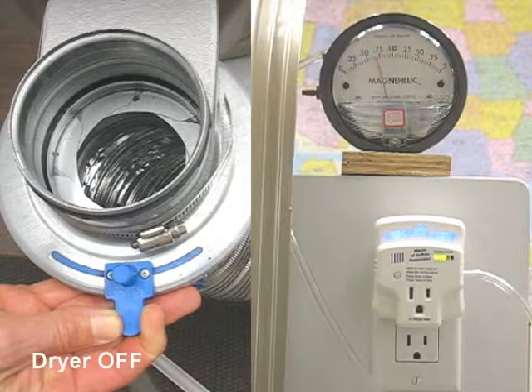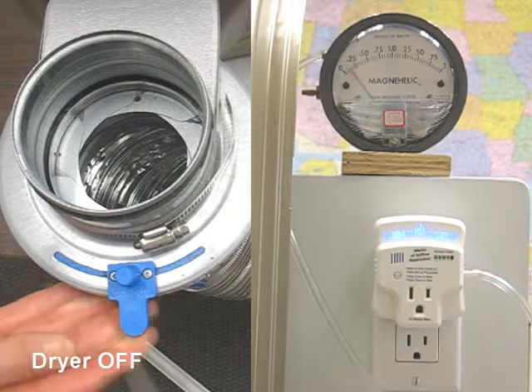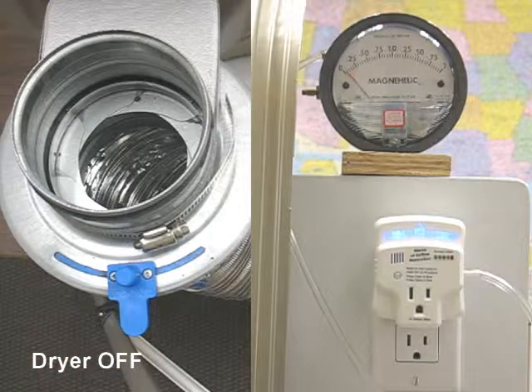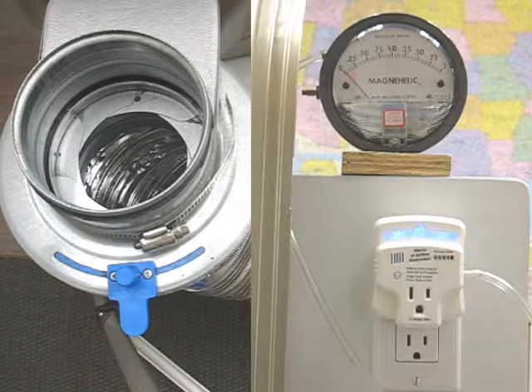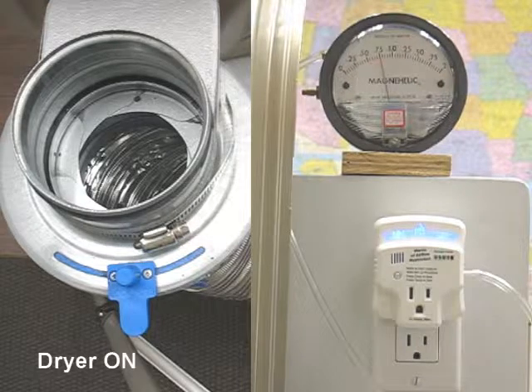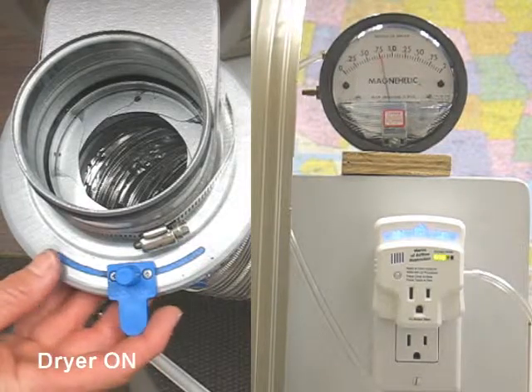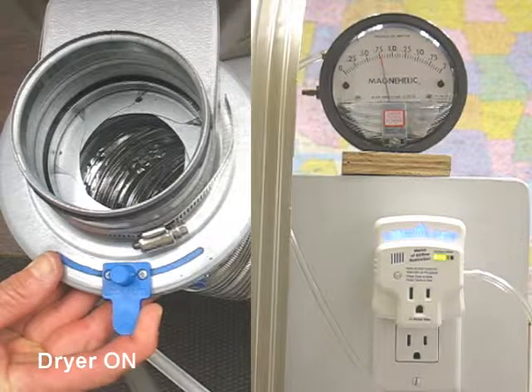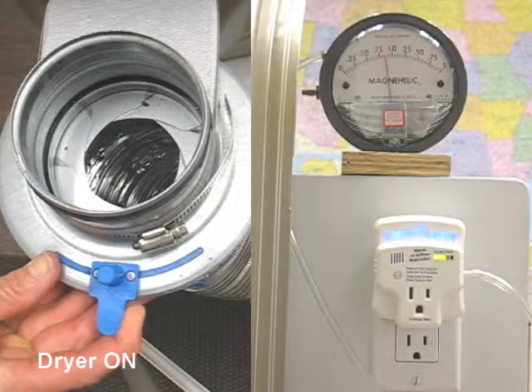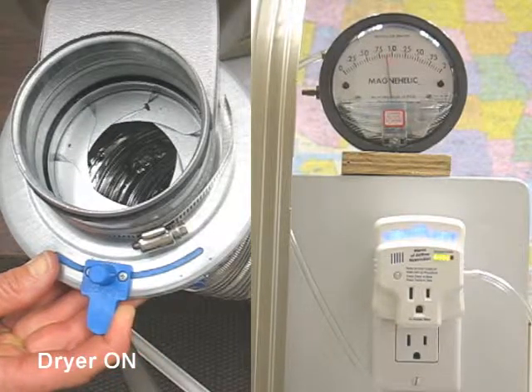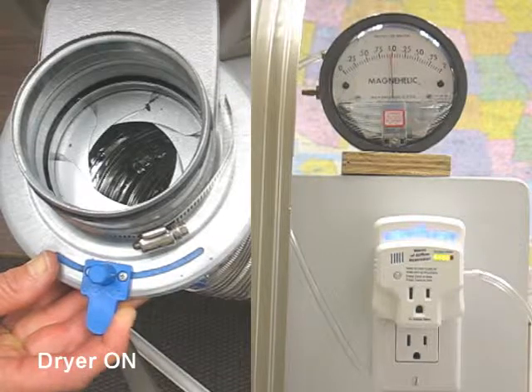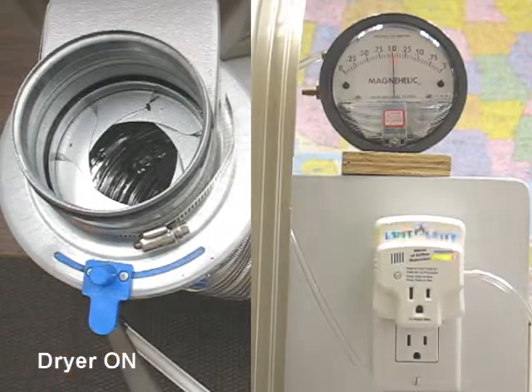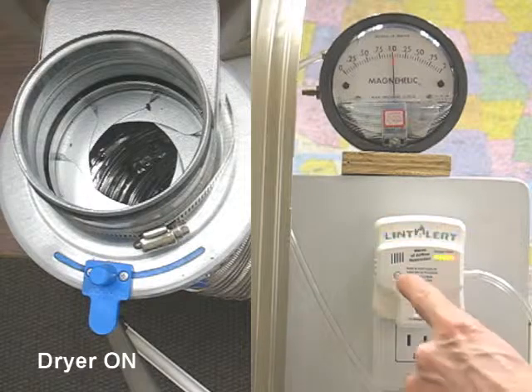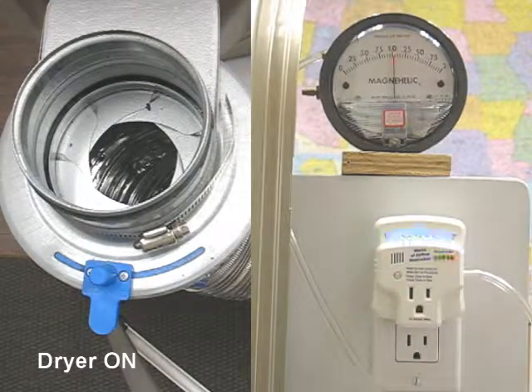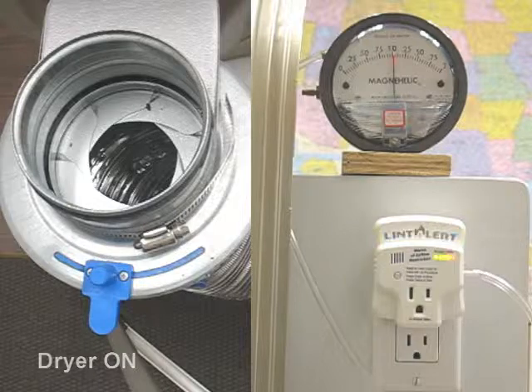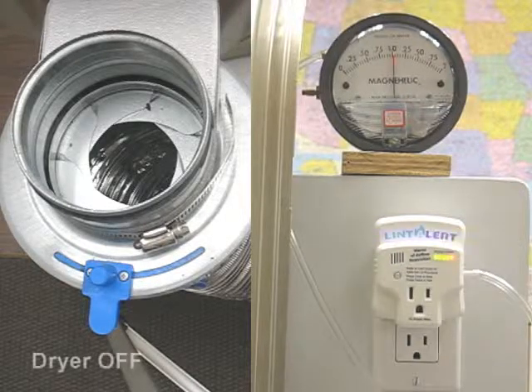If I turn off the dryer, the light bar goes out as no pressure exists. Upon restarting the dryer, the LintAlert reveals that the same levels of back pressure still exist in the system. Over time, as lint continues to build up, so will the blockage indicator until the final stage, which includes the combination of blinking lights and audible tone. The audible tone can be muted with a single push of the button. The blinking will remain as a reminder to assess the cause of the severe back pressure found.